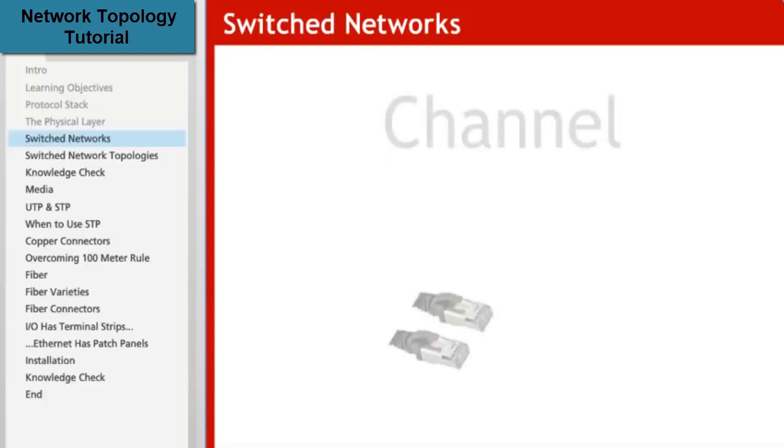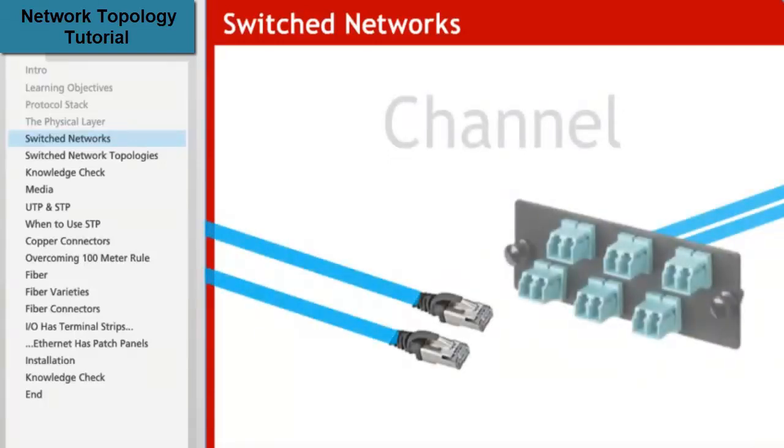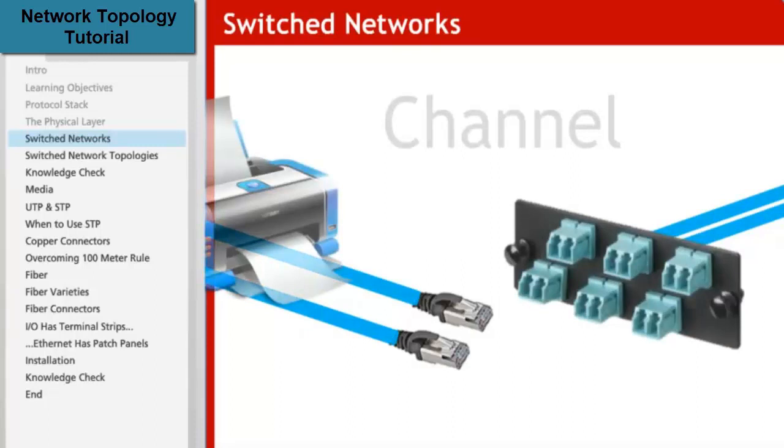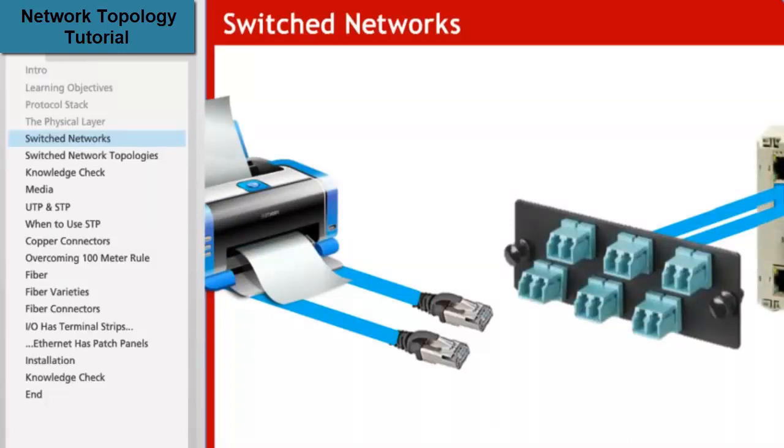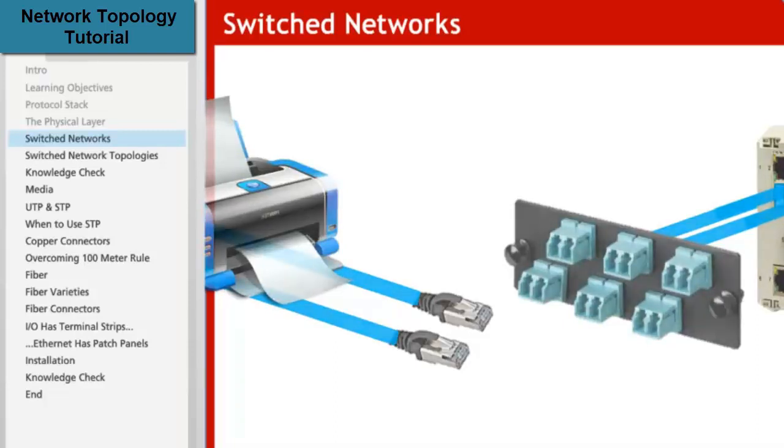The first general rule of such networking is this: we start with a physical channel that consists of passive devices like connectors, cables, and patch panels. If one end of a network channel is plugged into an end device like a computer, printer, or automation device, then the other end must be plugged into a switch. Along the way, there may be passive devices like connectors, wall jacks, patch panels, and patch cables, but the next piece of active electronics in the link must be an Ethernet switch.